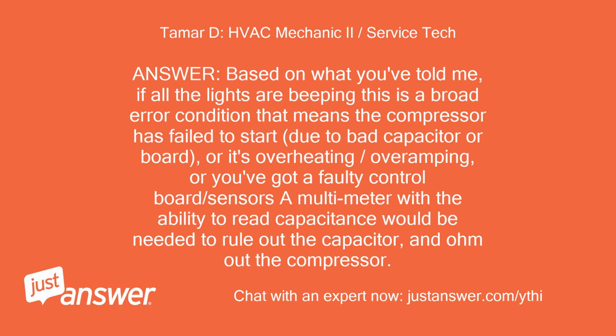Answer: based on what you've told me, if all the lights are beeping, this is a broad error condition. That means the compressor has failed to start, due to bad capacitor or board, or it's overheating, overamping, or you've got a faulty control board/sensors. A multimeter with the ability to read capacitance would be needed to rule out the capacitor and ohm out the compressor.